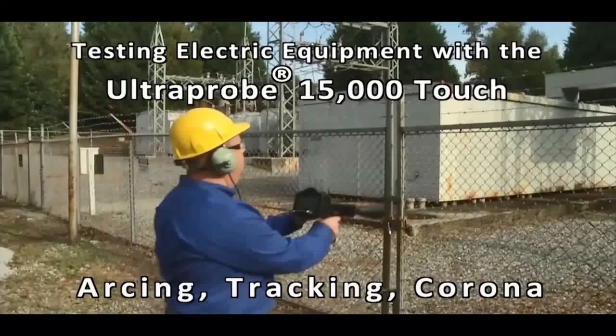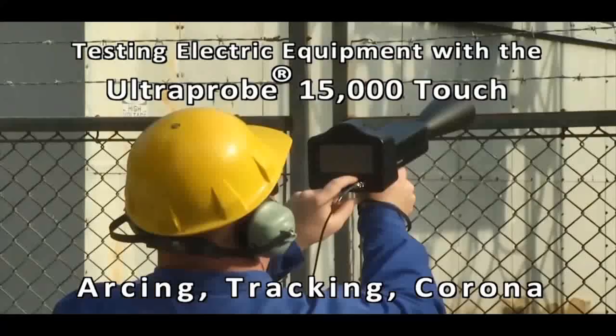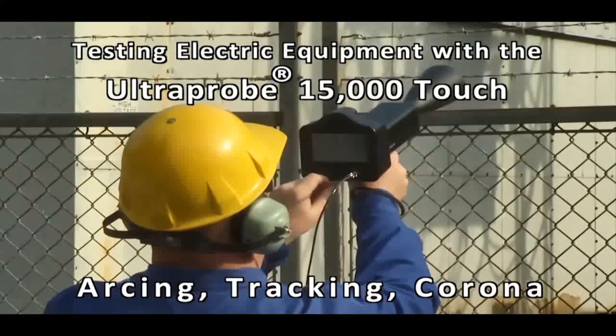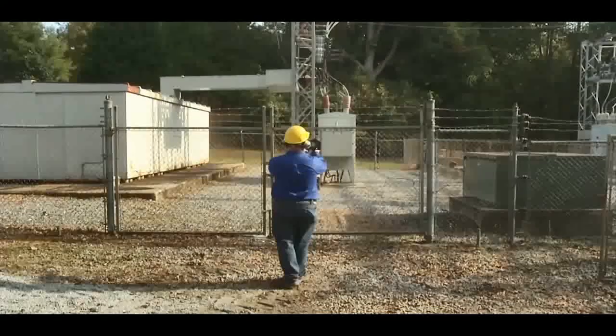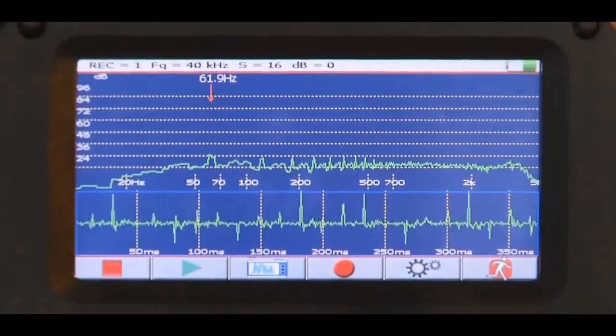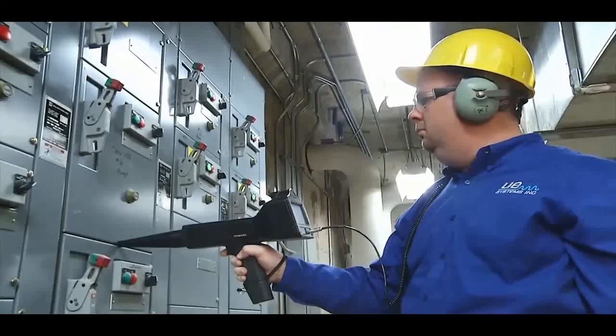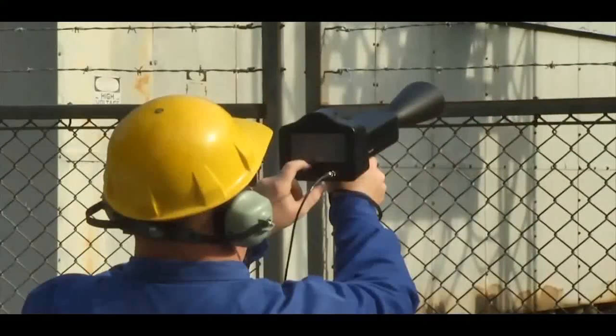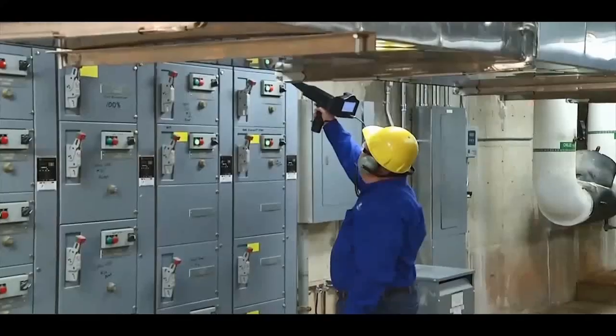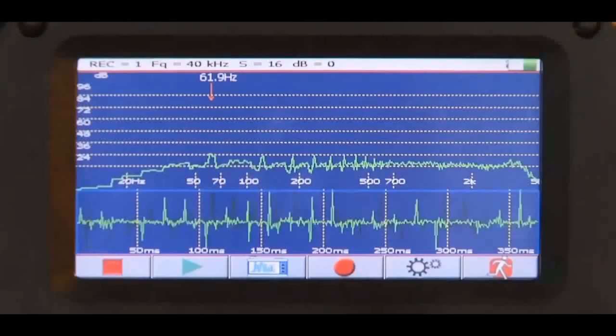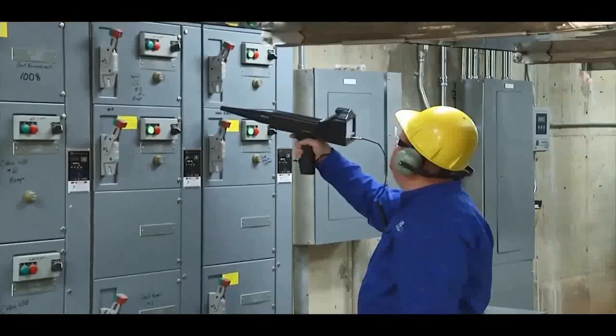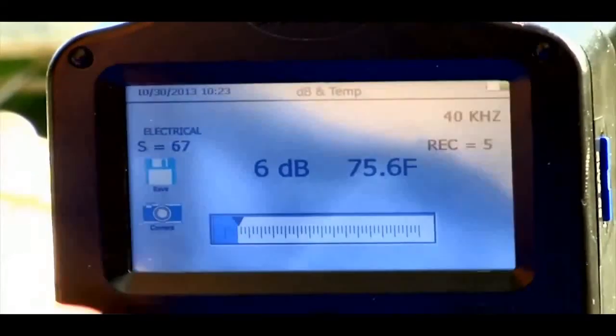When flashover happens, the results can be devastating. Detect and analyze potentially catastrophic conditions before they happen with UE Systems' remarkable Ultraprobe 15,000 Touch. Sense ultrasonic emissions of arcing, tracking, and corona in open or enclosed systems, whether heat is detectable with infrared or not. Scan at a safe distance with a long-range module or enclosed switchgear. This is the sound of corona. Not detectable with infrared. Record the sound and save it. Take a photo of it.